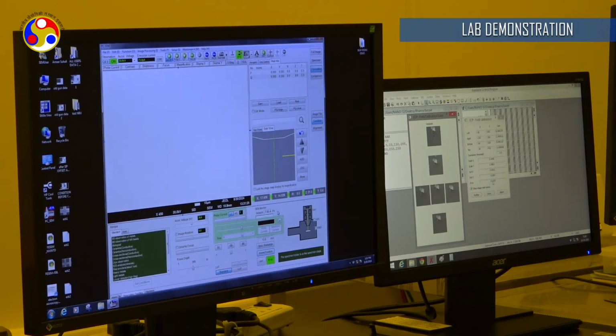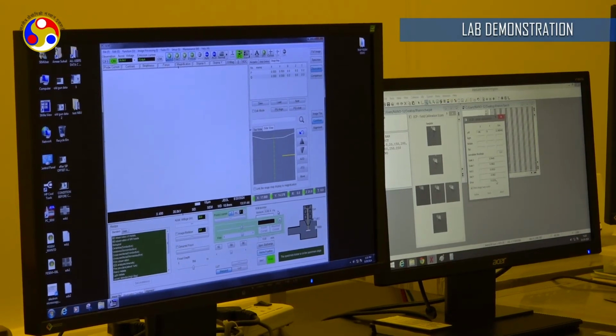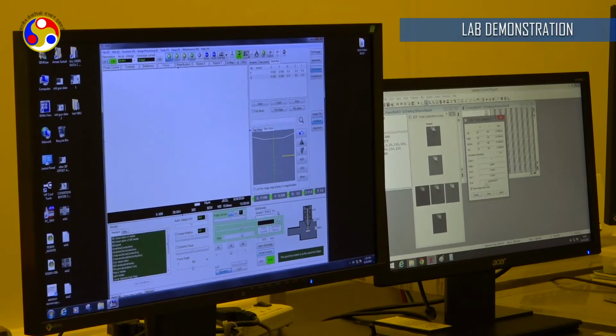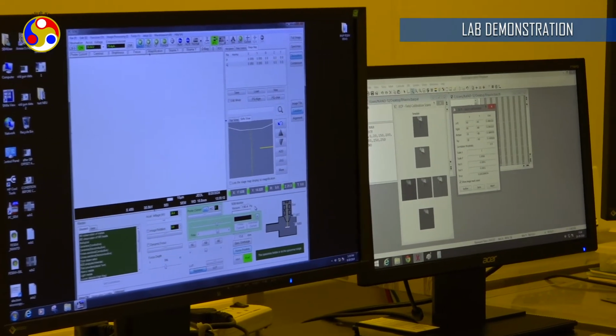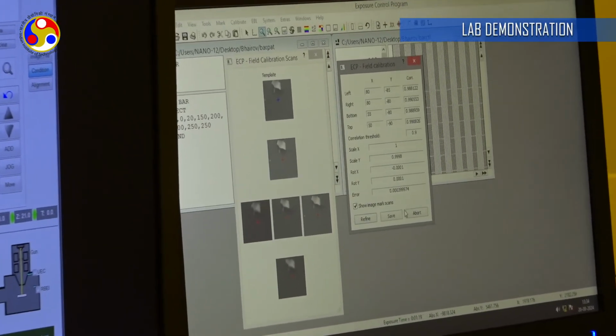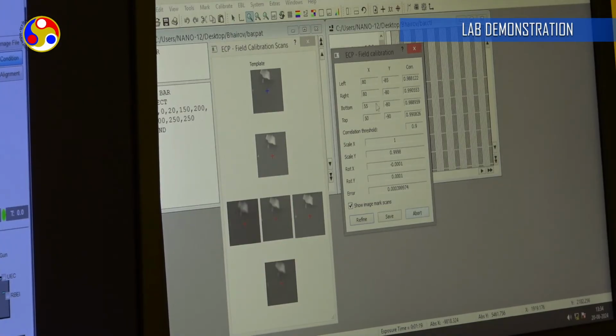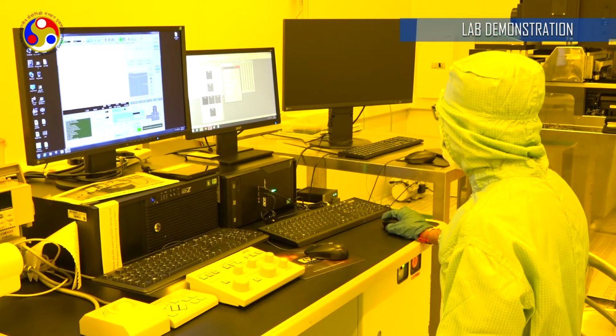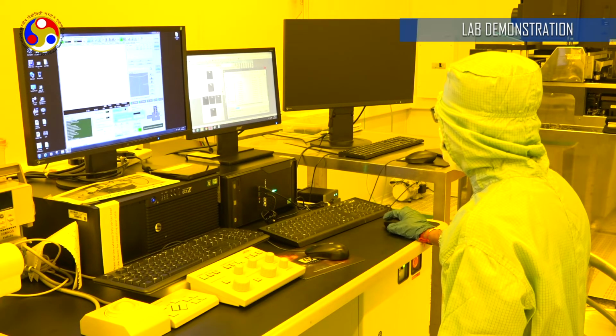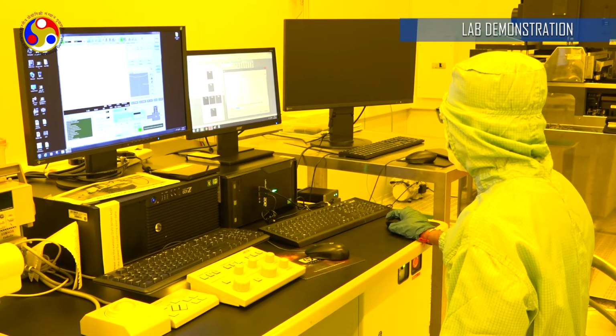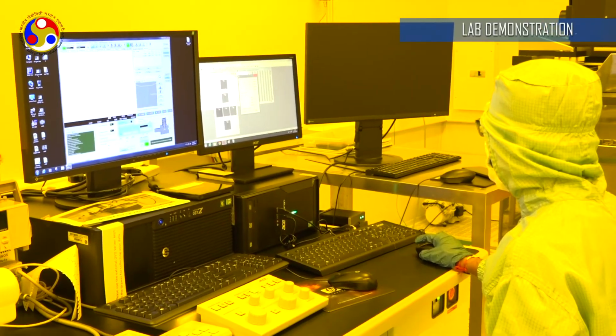We define the error to a limit of 0.0005 to 0.0003. So we will again refine this error, and we will wait till it goes to 0.0005 to 0.0003. Stop. Here we have reached this error limit. It is 0.0003, and we can start the process. Here we'll save these field calibrations, and we'll overwrite this file. A default file is there, default 0200, and we'll overwrite this. After that we'll click abort.